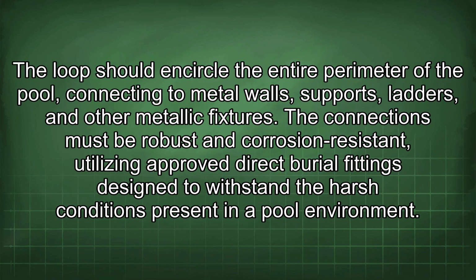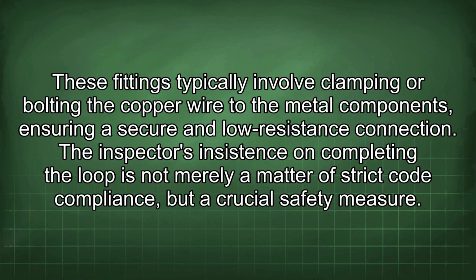The loop should encircle the entire perimeter of the pool, connecting to metal walls, supports, ladders, and other metallic fixtures. The connections must be robust and corrosion resistant, utilizing approved direct burial fittings designed to withstand the harsh conditions present in a pool environment. These fittings typically involve clamping or bolting the copper wire to the metal components, ensuring a secure and low resistance connection.